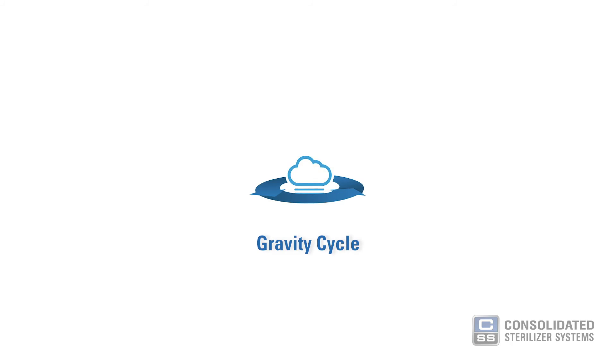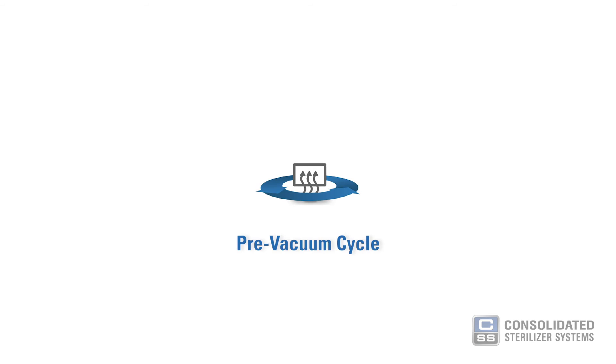Next up we'll talk about sterilization cycles. There are, in general, three standard and most popular sterilization cycles. A gravity cycle, which displaces air in the chamber by gravity. A pre-vacuum cycle, which mechanically removes air from the chamber using a series of vacuum and pressure pulses. And a liquid cycle, which is just a gravity cycle with a slower exhaust rate to minimize boil over.